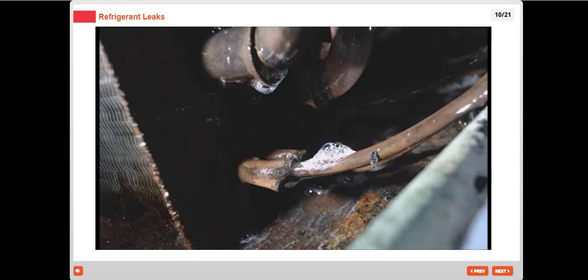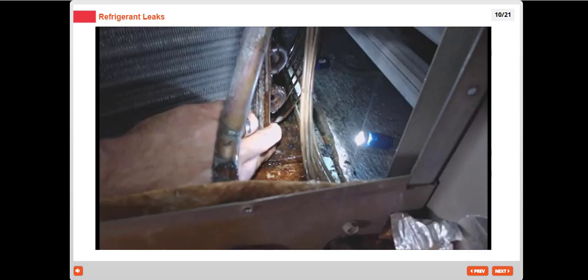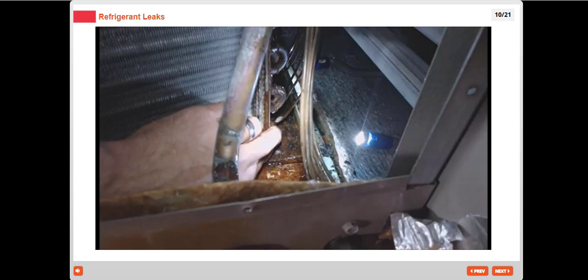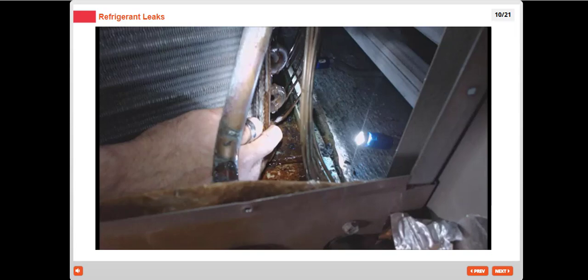So now we're backed up and you can see where the refrigerant leak is on the distributor tube on the evaporator coil. So that's one of them. There's another one towards the back. So that's how you find these leaks. You use the electronic leak detector and then you follow that up with the bubble leak detector too.